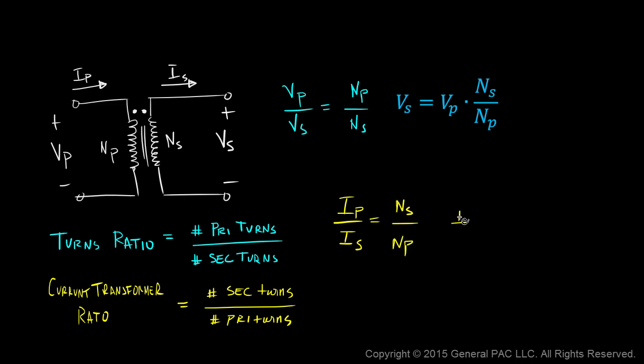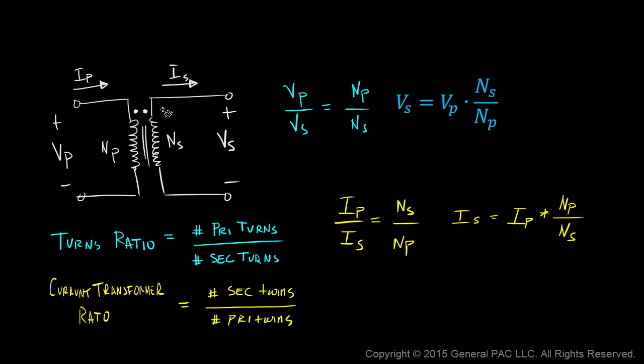If we solve for the secondary current, it equals primary current times the number of primary turns divided by the number of secondary turns. The purpose of a current transformer is to transform primary current, which is a high value, to secondary current, which is a low value, but to transform them proportionally.